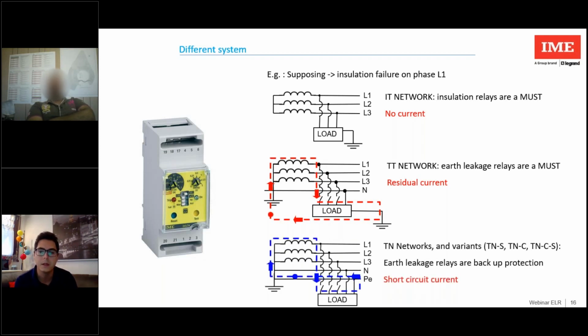In the TN system and its variants, the earth fault current returns to the power supply node through a direct metal connection, PE or PEN, without practically affecting the earth rod. In practice, it is a short circuit. For this reason, a thermal magnetic circuit breaker could be enough.